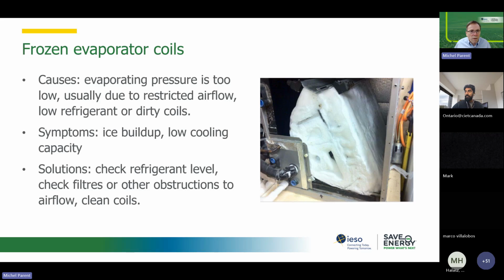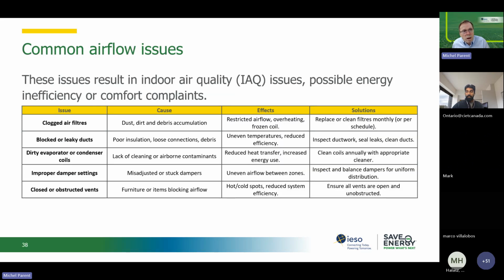And here's an example of that really, really frozen evaporator coil. Another issue we want to talk about is airflow issues. If you've got low airflow, it can be due to a lot of leakage in your ductwork. You may have tenant fit-ups and people will push a VAV box in the ceiling space, and it's no longer providing air to the space. You may have flexible ductwork that's disconnected. All of those are very common issues that will reduce your effective airflow delivered to the space.